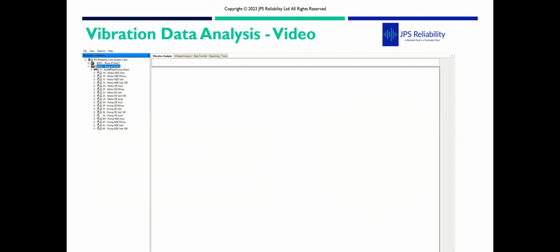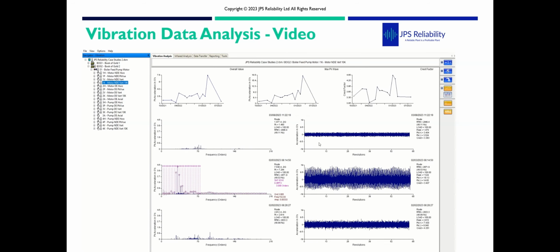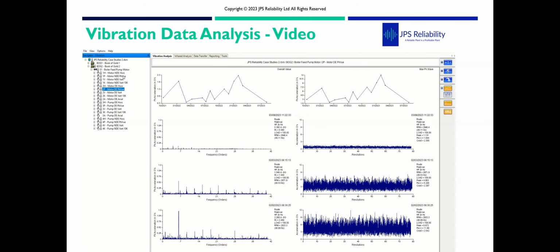So here we are on the vibration analysis software. We can see our folder, the Book of Gold 2, and this is our case study training analysis number 1. What we collect mainly is vibration velocity, acceleration low end and acceleration high end, and PeakVue. So here we have our velocity, our low acceleration, our high frequency acceleration, and here our PeakVue data. We've been trending this one for a while.